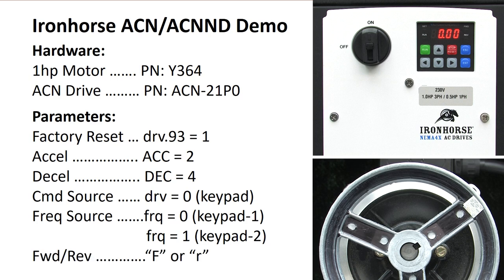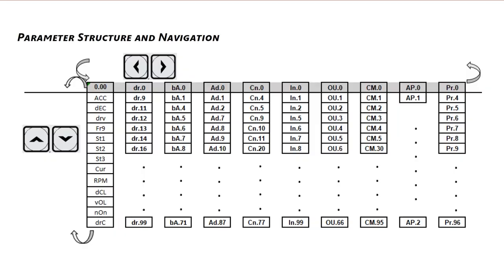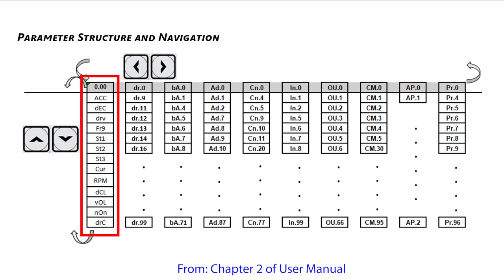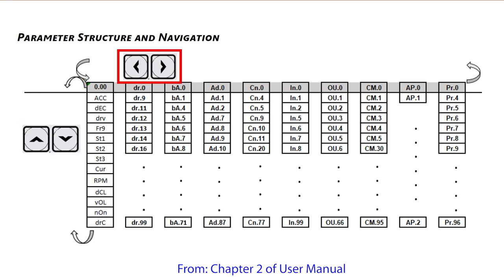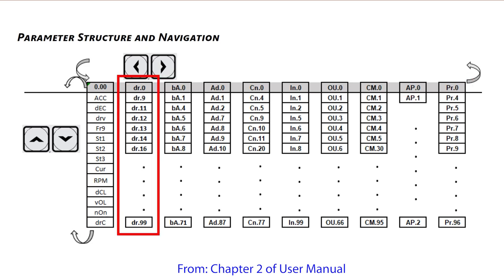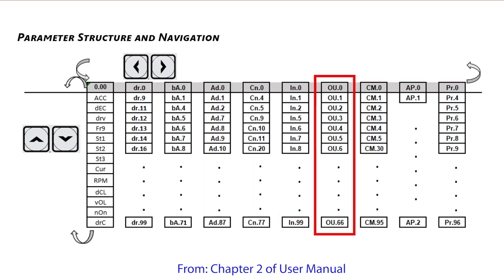The cool thing about the ACN drive is while you can rotate through the parameter groups using the left and right arrow keys, the drive brings the most common parameters up to a top level operational menu that you access using the up down arrow keys. I love this chart in Chapter 2 of the user manual. It shows you how you can scroll up and down through the most often used parameters or you can scroll left right to access all the parameter groups and then use the up down arrow keys to access each group's members.